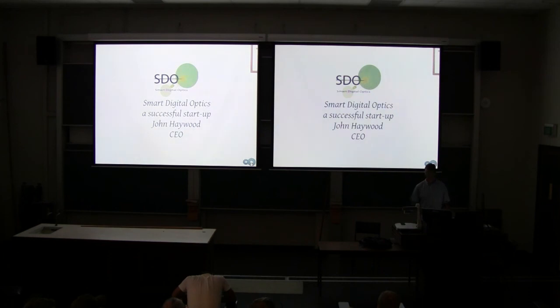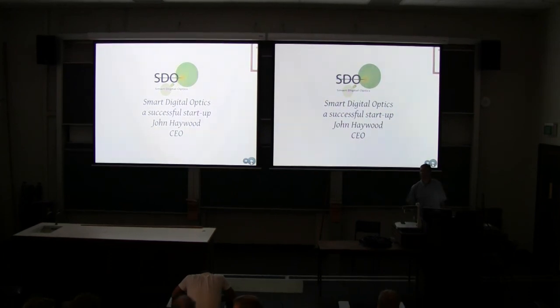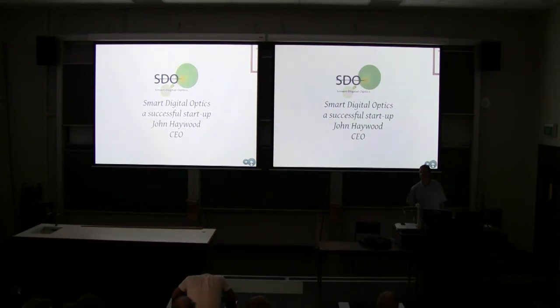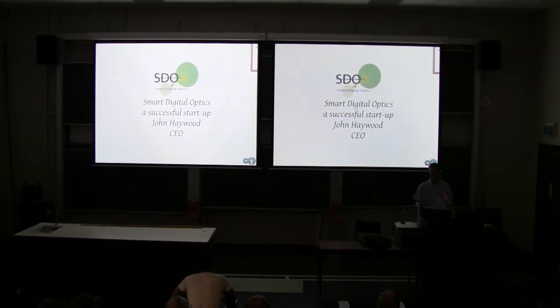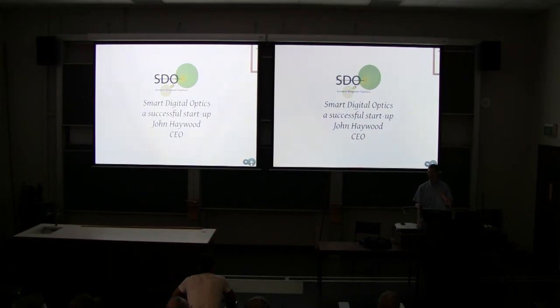My final question: is this self-calibrating, or does it need external calibration? It does need calibration. The fiber that we use in the sensor head can vary by about 5% in its sensitivity to current, depending on the spin pitch and fiber pitch in it. So we do need to calibrate each one for sensitivity. Once the calibration's done, it's fit for life.